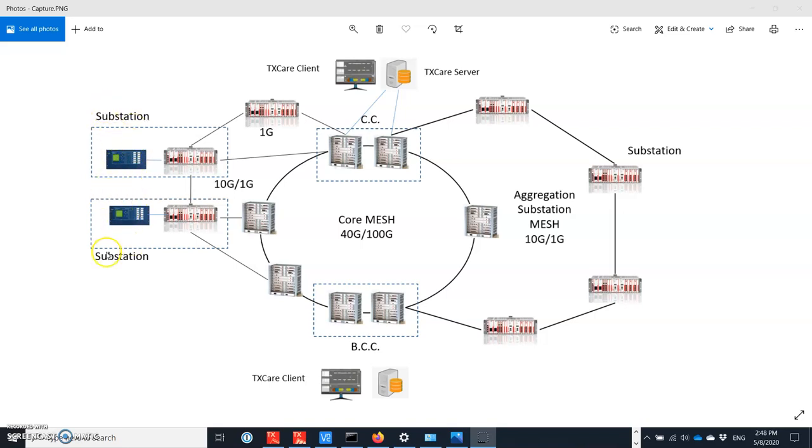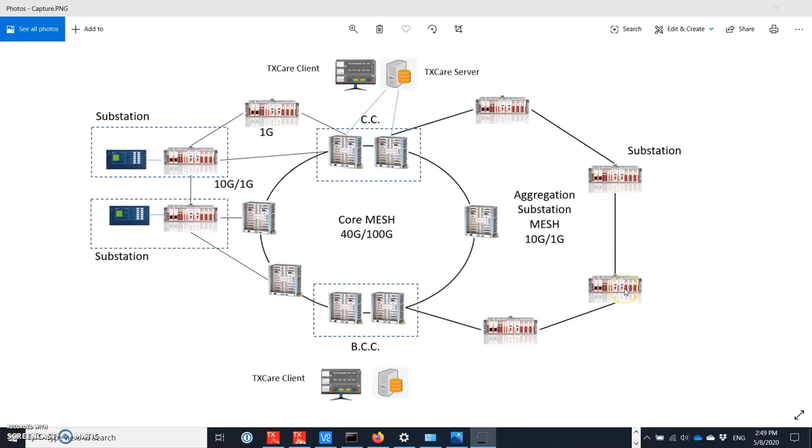You may have a direct path to connect the relays and you may have a secondary backup path, but in some cases you may have a third or a fourth path you want to take advantage of. So that's what I'm going to show you. I have a live network here with the relay tester and I'm going to demonstrate this.